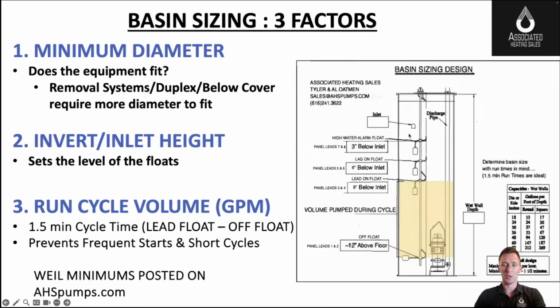I'm going to ask you where your lowest inlet comes in because I'm going to start my float tree right after that inlet, below that inlet I should say, so we don't get fluid backing up into the inlet. Every 3 inches, we put a new float, and we want the largest distance between floats, between the off float and the lead or on float. So this pump operates at a longer cycle, or its longest cycle it can. We're often limited with basin depth.